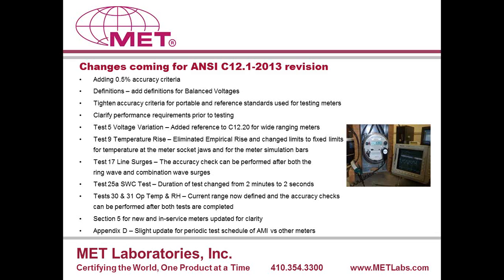Test 5, I don't think I really need to read through all these. I just wanted to list them for you to read. But test 5, voltage variation, there's going to be some changes there for wide-ranging meters. Some empirical rise changes to the limits out of the temperature rise criteria, along with some details on where to attach thermocouples, where to measure those temperatures during testing. So really helping better define the criteria and the procedures for running through those particular tests.